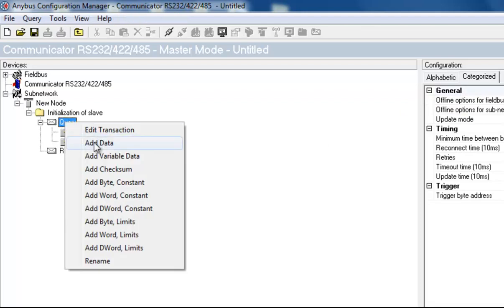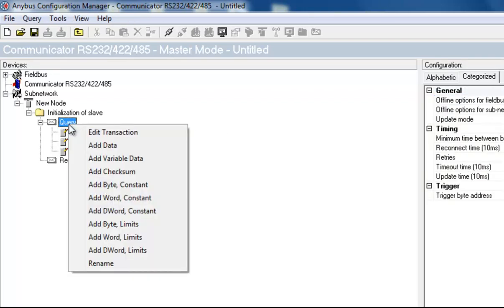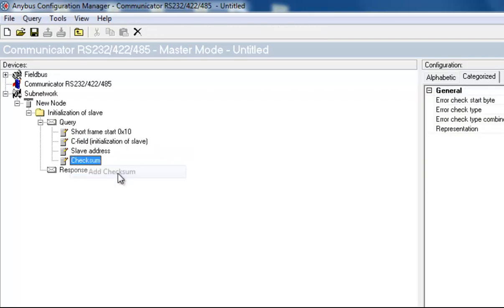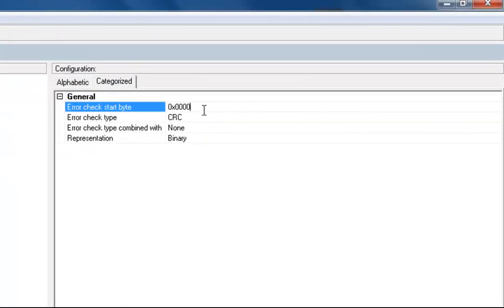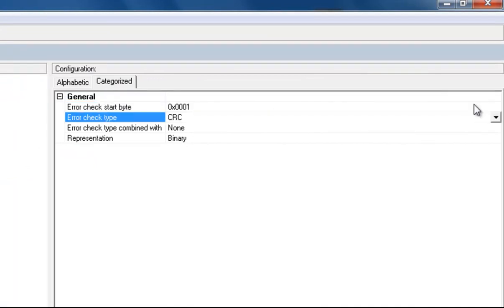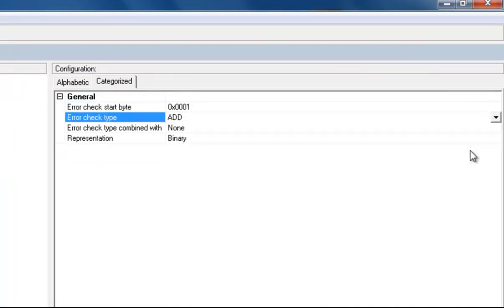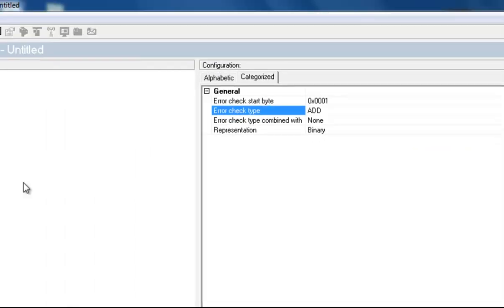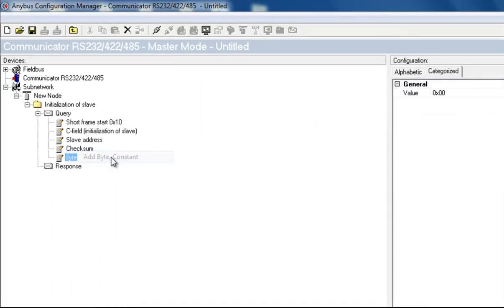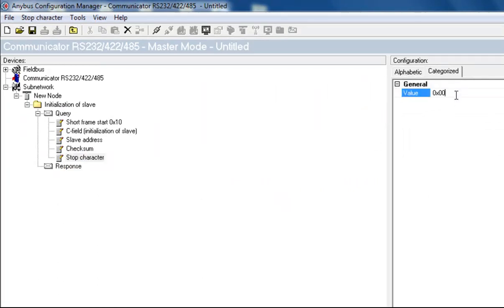Next, I add a slave address, which is 1. And then a checksum, which starts with byte 1 and has an error check type which is ADD. This stands for Addition. At the end, we add a final byte, a stop character, which has the hexadecimal value 16.